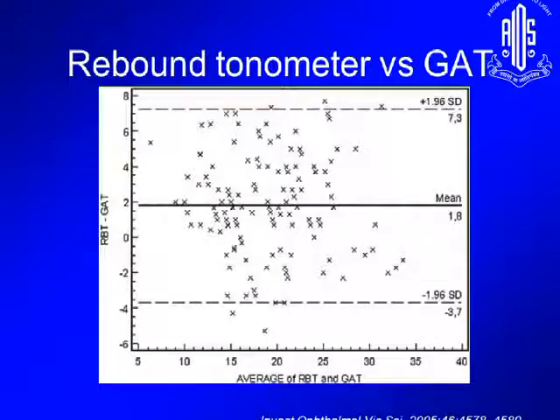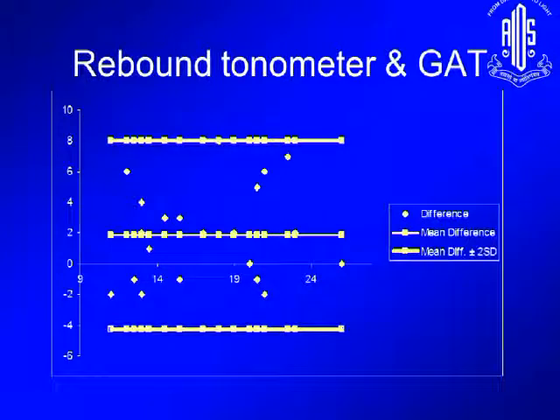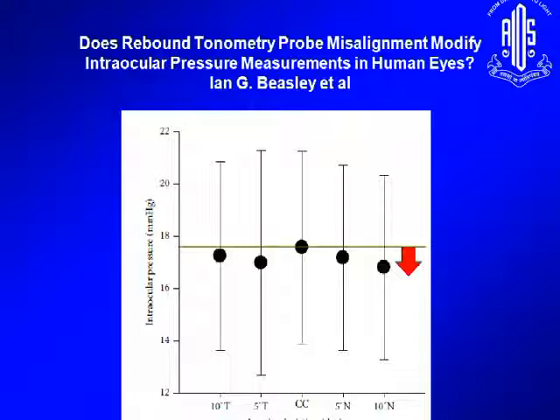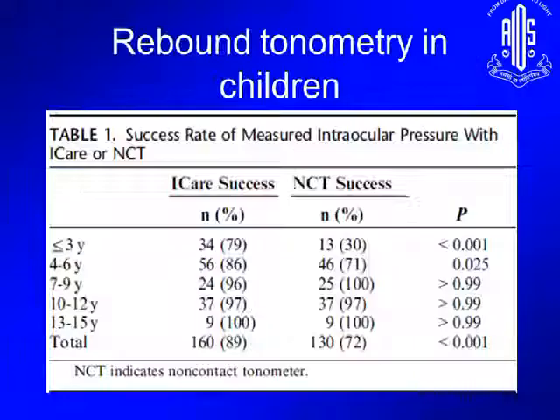If you compare the Rebound tonometer versus Applanation, you find that it consistently overestimates intraocular pressures by about 2 millimeters, and the range of this difference can be between -4 and +7. Again, fairly large. This is our own experience with the Rebound. It replicates what the other studies have shown, not very much difference. One of the concerns with the Rebound is that if you are not keeping it straight vertically, but slightly sideways, does that affect intraocular pressure? It does seem that if you are more than 10 degrees off the vertical, you can have some difference in the intraocular pressure. So it's important that you're vertical on the cornea.